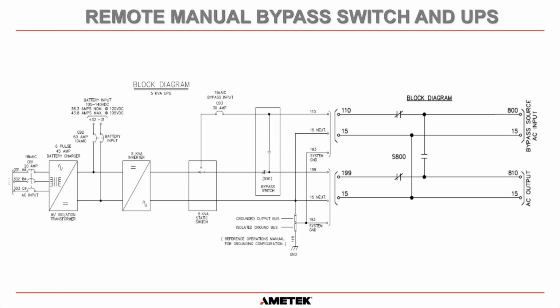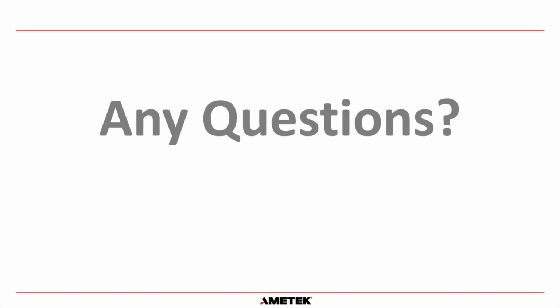Good question, Abdul. In our DPP systems and in our DSE systems, so in all of our modern UPS systems, we have what's called a crash pad on our inverter static switch control board. There are two black push buttons on the inverter static switch control board. One says inverter to load and one says bypass to load.